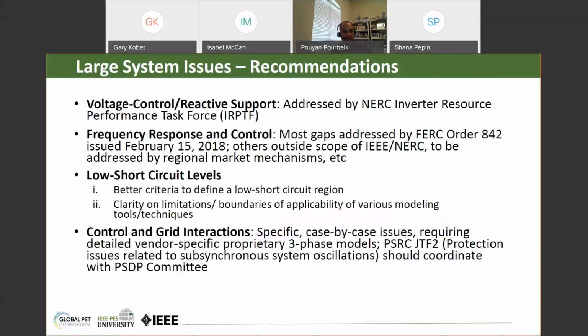Really, these were high-level recommendations. We had some recommendations on how there's a need for a good qualified definition of voltage control and reactive support. Some of this was actually addressed by the NERC Inverter Resource Performance Task Force, and is now being further addressed by P2800, which I'll mention in a minute. With FERC Order 842, which came out in February 2018, a lot of these issues around frequency response were addressed, at least for the North American market. In the FERC order, they say that capability is needed. They give recommended levels for droop and deadband, and they further clarify what we just discussed, that you do not have to carry reserve because there's opportunity cost associated with that, but you just have to have the capability to do it in case you're curtailed.